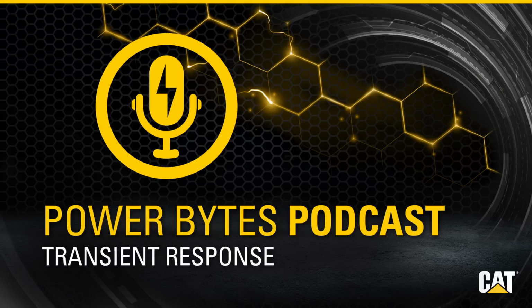So I understand there are some industry standards to define how transient responses should be measured. I did a little legwork and found ISO 8528. Can you fill us in on this standard and its application? Yes. So ISO 8528-5 is the most common standard for transient response. This standard has two primary concepts that are critical to evaluation of generator transient performance. The first is that the load steps applied to the generator should be based on the BMEP of the generator. As the standard states, a higher BMEP usually makes loading in several steps necessary.